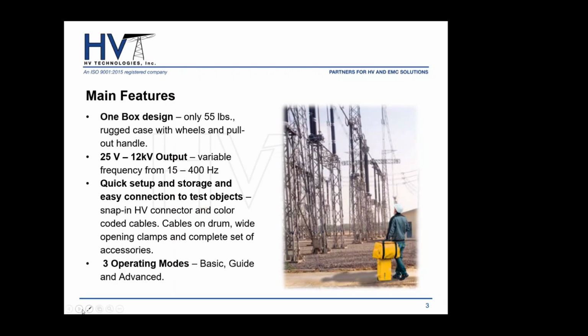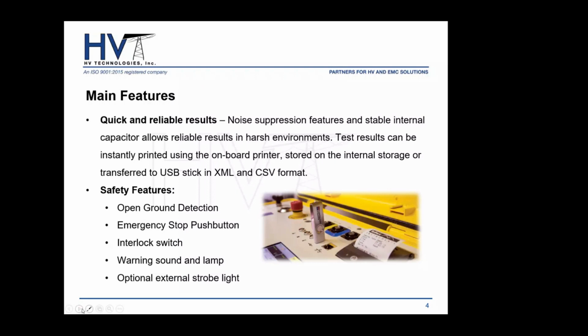But also, the MIDAS Micro allows us to have quick and reliable results. We have reliable results because there are noise suppression features, and like I mentioned, the internal reference capacitor is an SF6 gas capacitor, very stable, and this allows for reliable results even in harsh environments. So if you have this instrument out in your substation with high voltage overhead lines, the instrument has features that will automatically switch on noise suppression to make sure that your measurements are as accurate as possible.